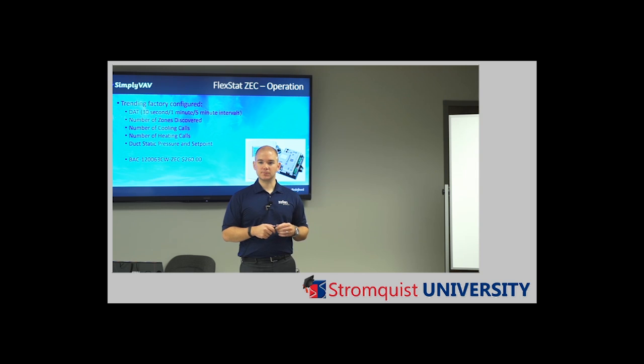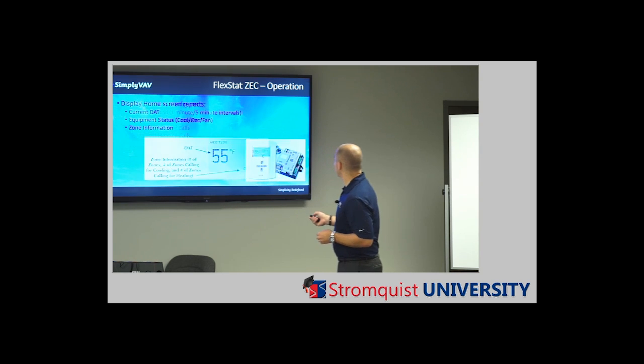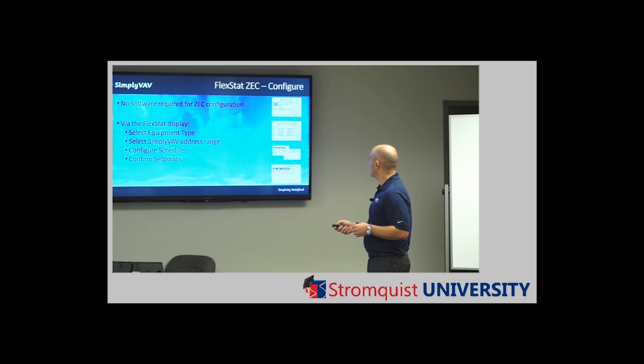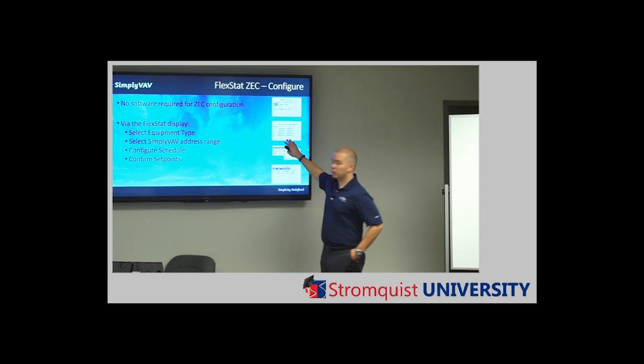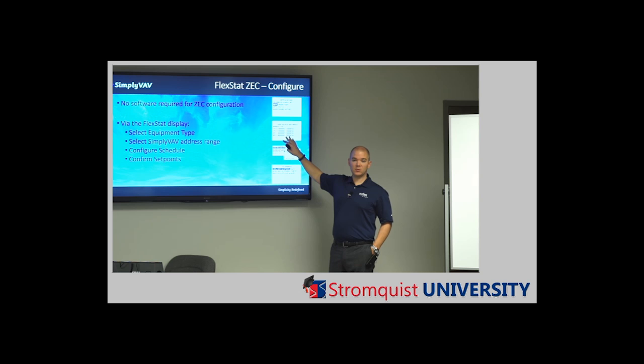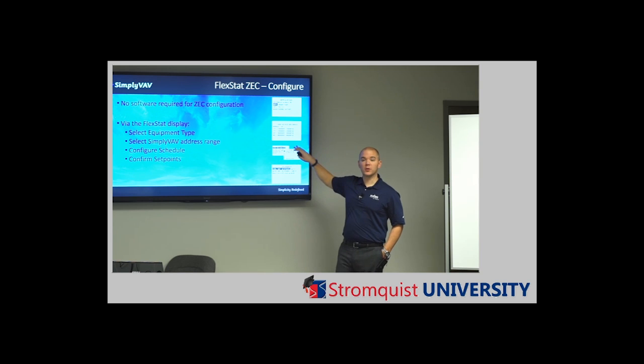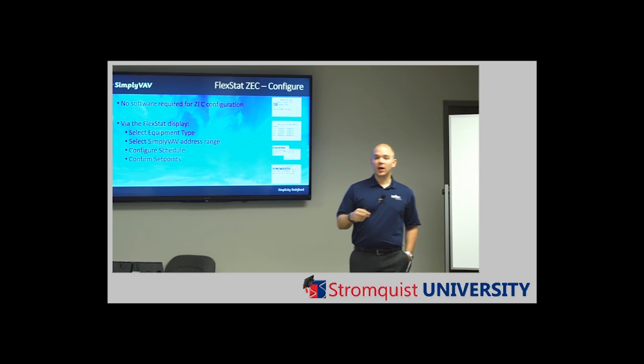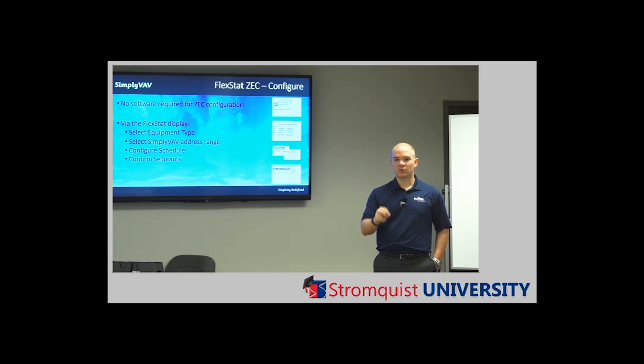Now, I assume that you can have multiple flex stats on a system and you can tell Simply VAV which address they... Right, so if we go back here, the internal programming will allow 4 ZECs on one BACnet network before you have to deal with any conflicts. So you'd pick 1 million instance range, 2 million, 3 million, or 4 million. If you want to grow beyond that, or you have a custom instance range, say a building owner says use 10,000, 20,000, 30,000, you'd have to go into the program and change what those addresses are.